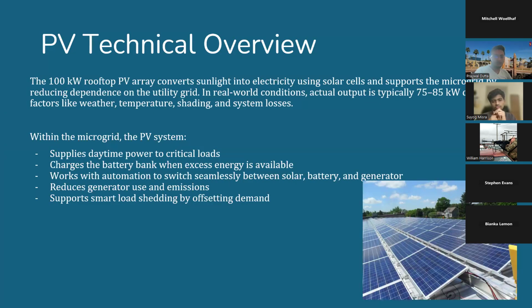The 100 kilowatt rooftop PV array takes the energy from the sun, converts it to electricity, and the actual output that we expect to see is somewhere between 75 and 85 kilowatts. That's due to a variety of factors, mostly weather, though. So this will allow us to reduce overall energy demand on the grid, reducing our dependency and our operating costs. And it also works with the automation to supplement the generator output to allow more loads to be powered during a long-term outage. Well, at least as long as the sun's shining.